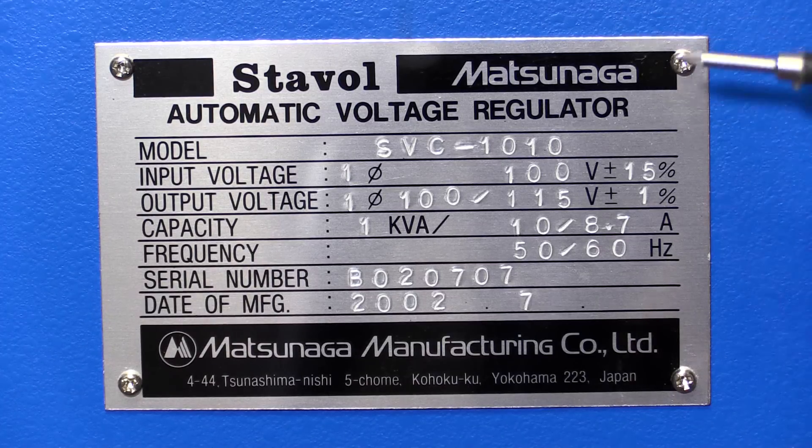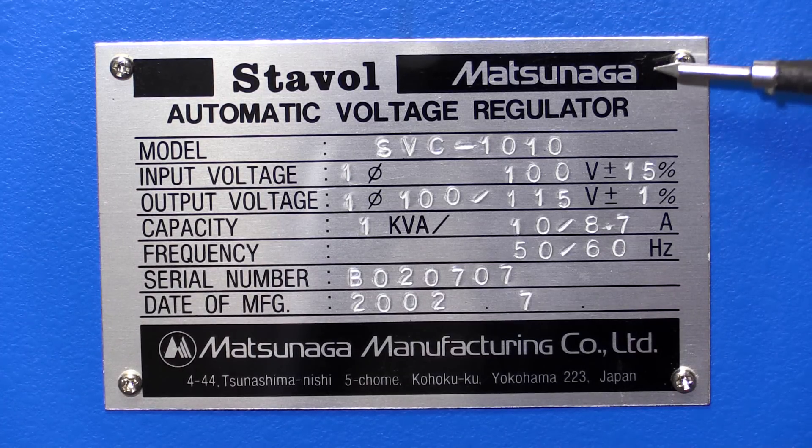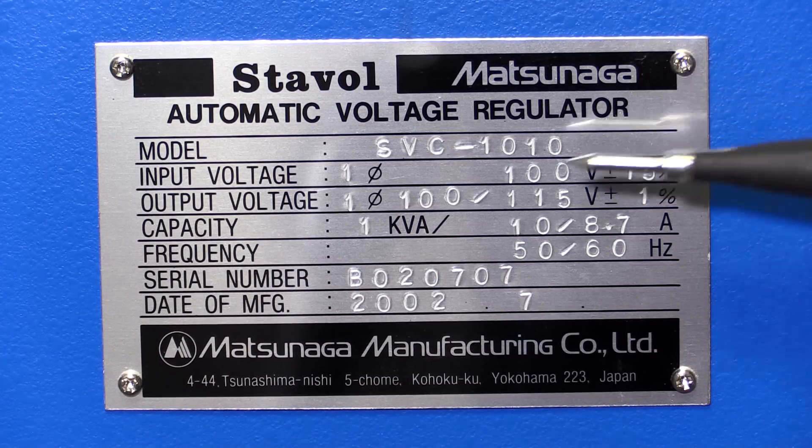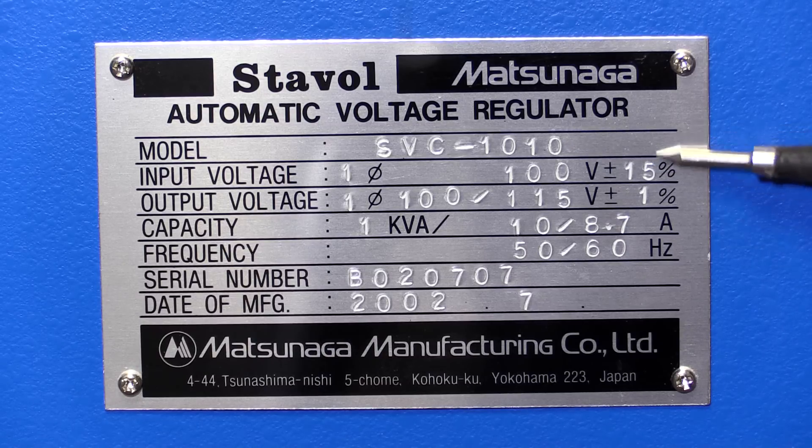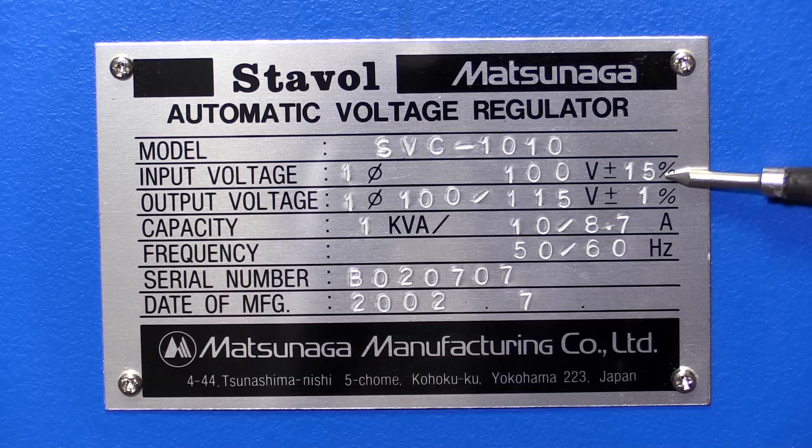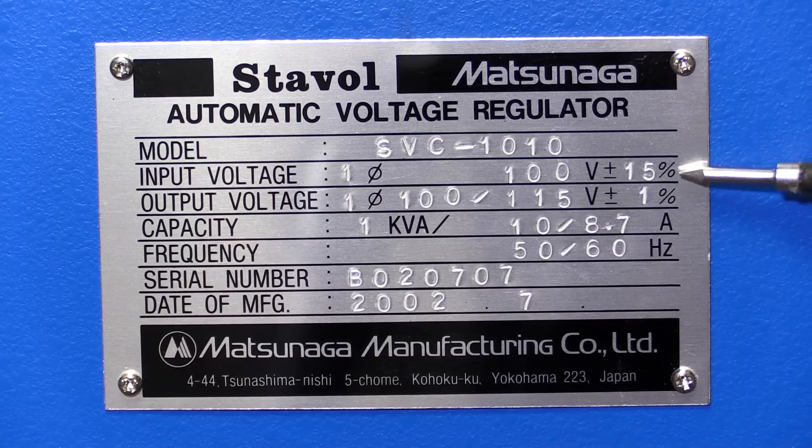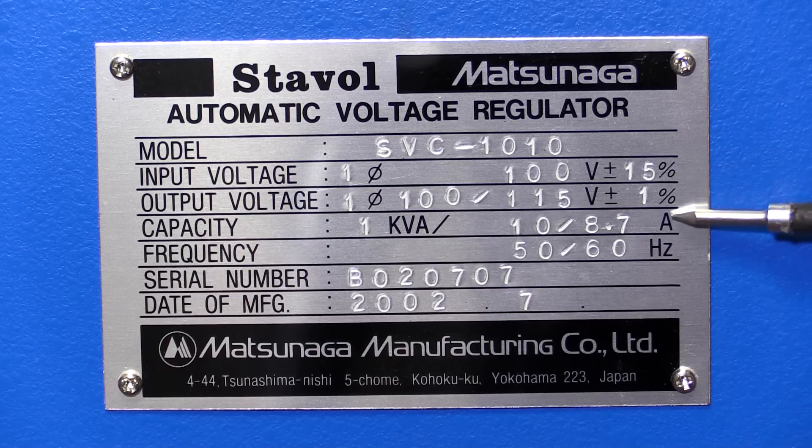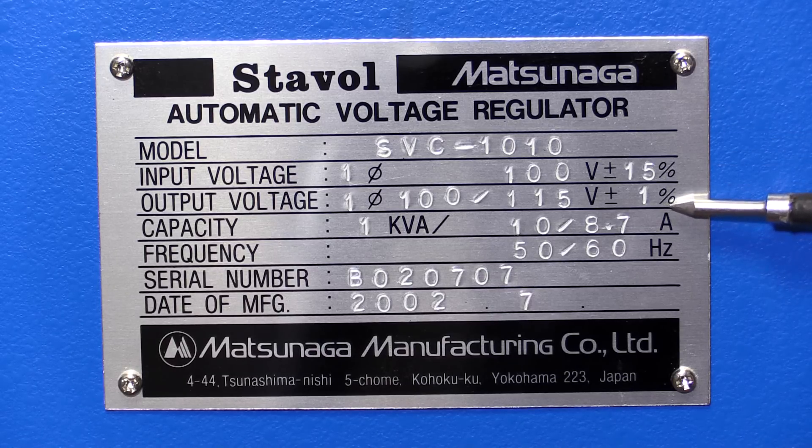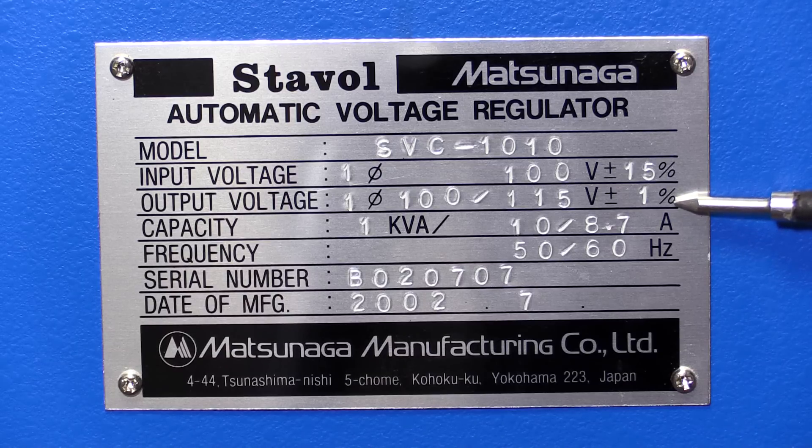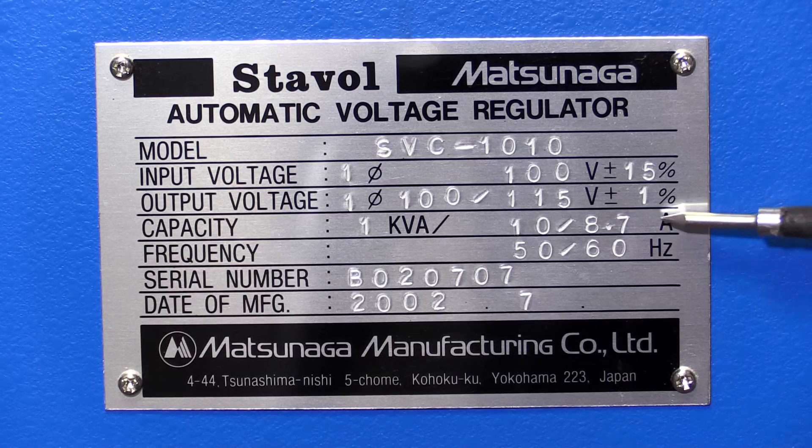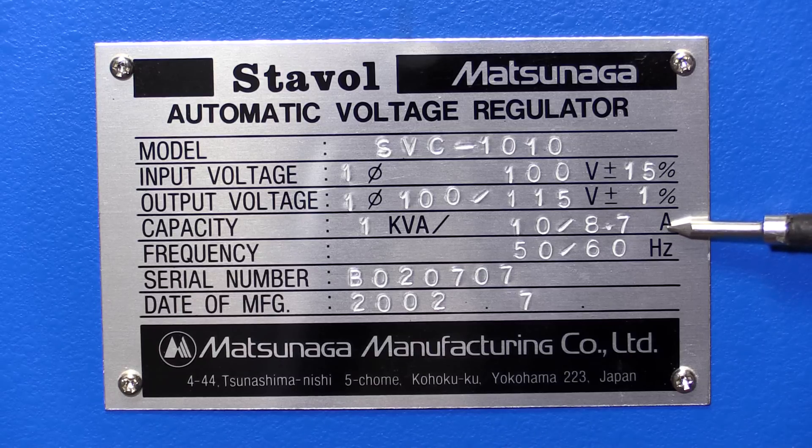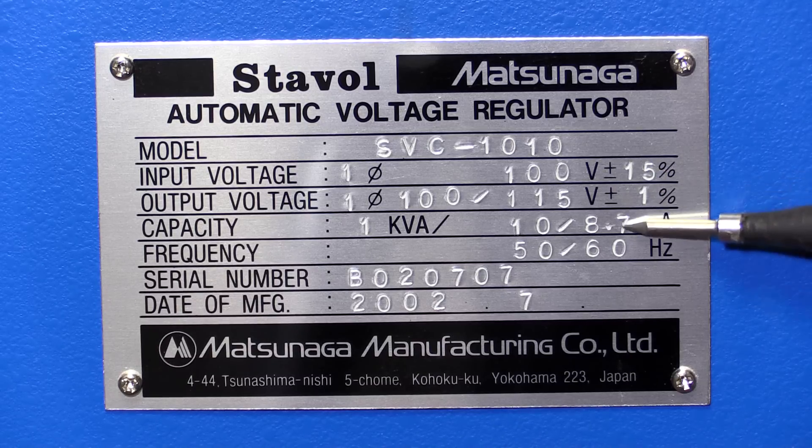So here we've got the data plate on the back. It's a Matsunaga brand, automatic voltage regulator, SVC-1010, input voltage 100 volts plus or minus 15%, so you can go up and down by 15 volts, output between 100 and 115 volts plus or minus 1%, 1 kVA.